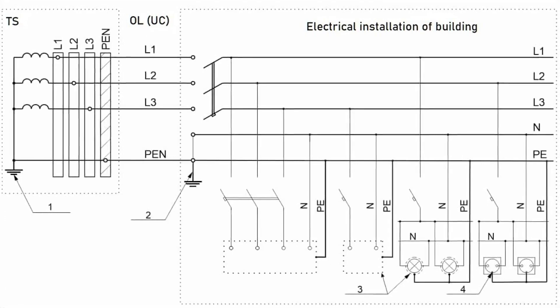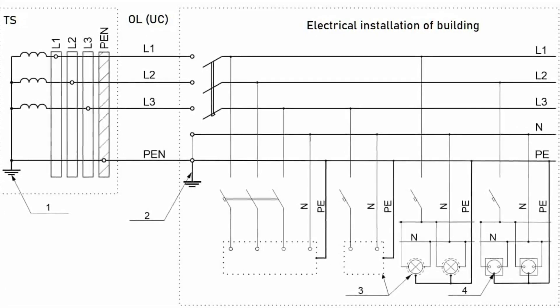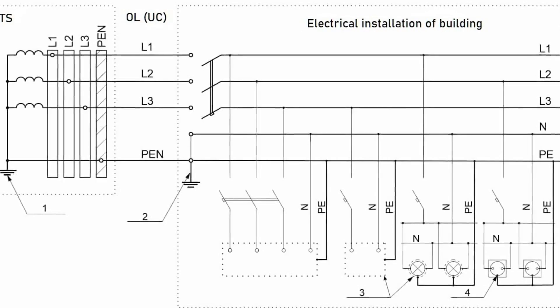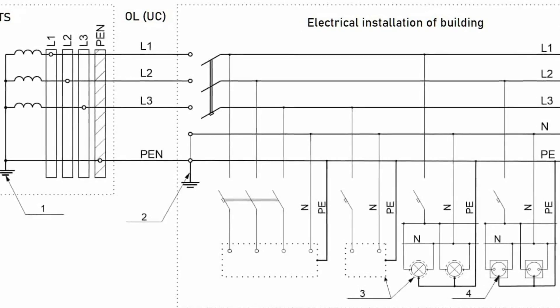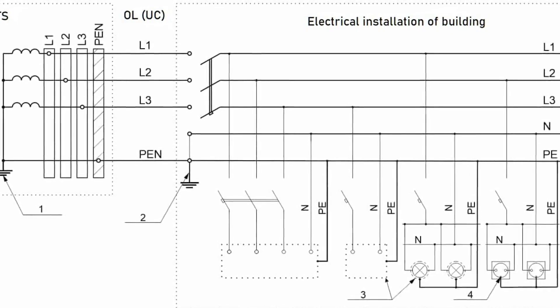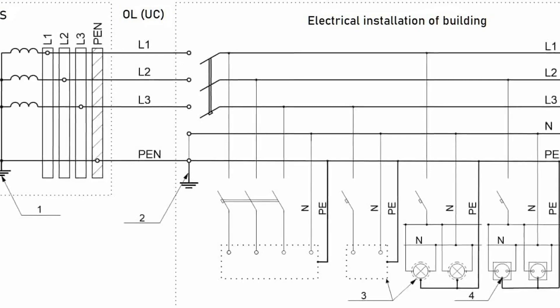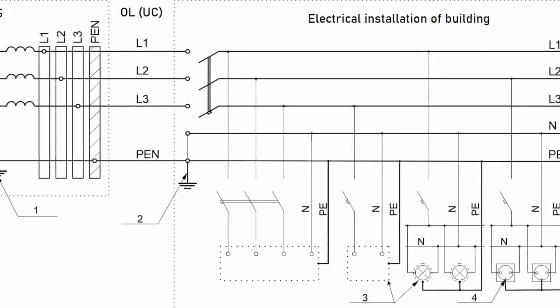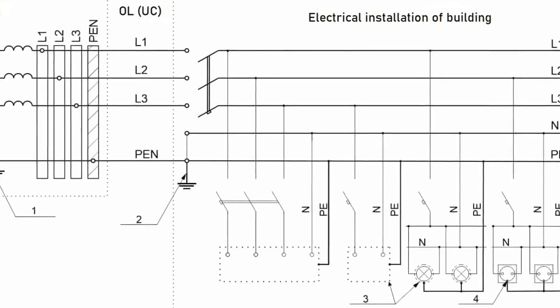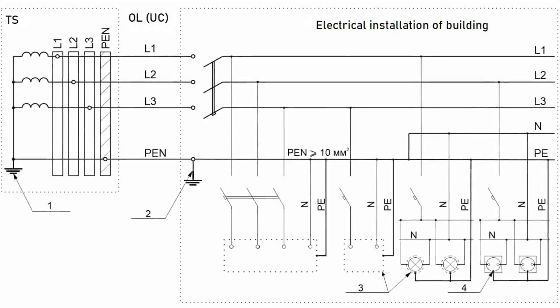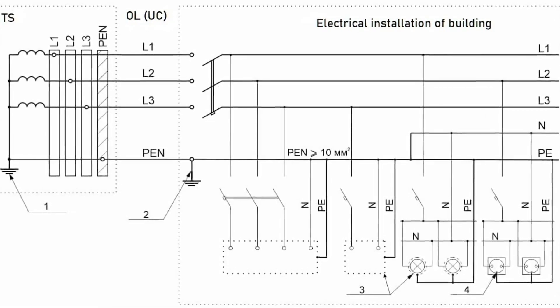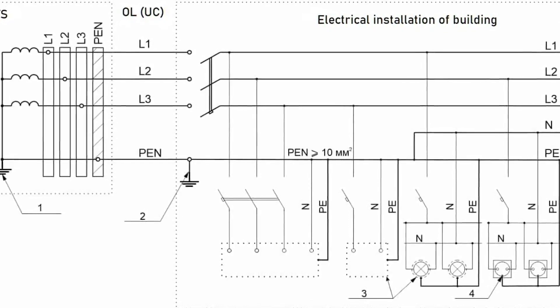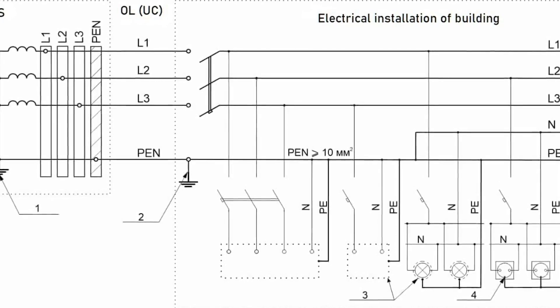With the TN-C-S type of system earthing, the PEN conductor is always separated into a protective conductor and a neutral conductor at some point in the electrical installation of a building. This separation can be affected at the origin of the electrical installation — at the input terminal or at the protective bus bar of the switchgear (figure one). This should be done in the electrical installations of residential and public buildings, commercial establishments, and medical facilities. The PEN conductor can also be separated at the input terminal or protective bus bar of another switchgear connected to the main switchgear via a distribution circuit that has the PEN conductor as part of its conductors (figure two).